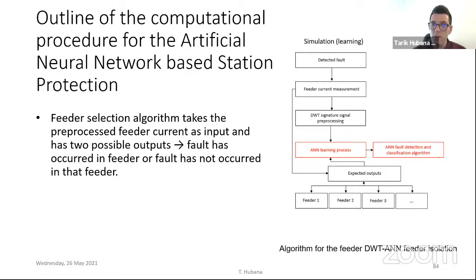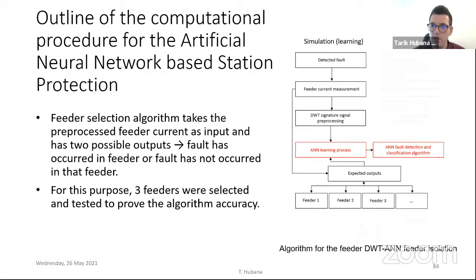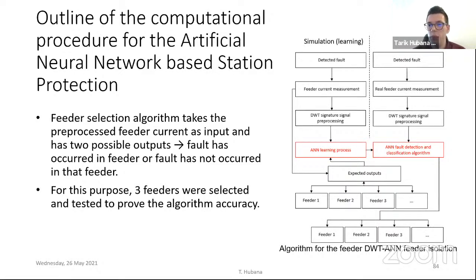So the feeder selection algorithm, which is an improved algorithm besides this detection and classification algorithm, takes the pre-processed feeder currents as inputs and has 2 possible outputs: fault occurred in that feeder or fault did not occur in that feeder. On the right side, we see how this algorithm for the feeder isolation works. Again, we pre-process these signals with the DWT in the same manner like the voltages. And once trained, this algorithm can be used in order to detect the faulty feeder in our part of the system.